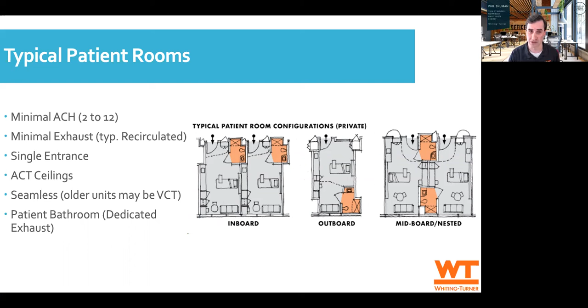So what do we have to do in order to modify these rooms? Well, we need to increase the air changes per hour to a minimum of 12. We have to seal off certain things.